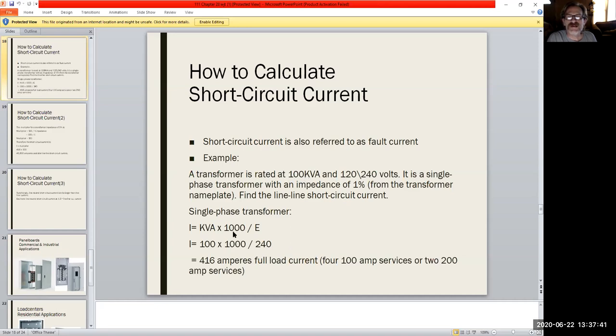So the K is the 1,000. So we have 100. So 100 times 1,000 divided by the maximum voltage we're allowed to use here, which is 240. If you just draw out your math, what you end up coming out with is 416 amps full load current. So if you were actually going to have this one going into your house, what you would be required to have would be 4 100 amp services. Yep, that would be 4 different 100 amp panels, or 2 200 amp services. And that would be 2 separate panels with 2 separate disconnects to them. That's what we would be rated for in this case.